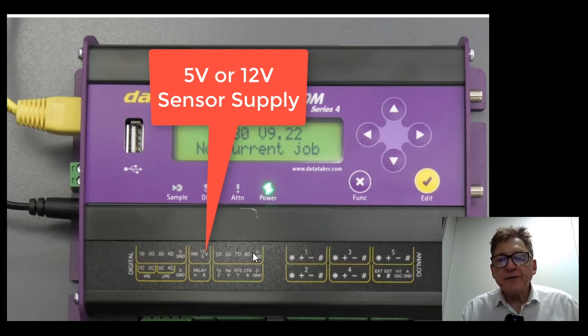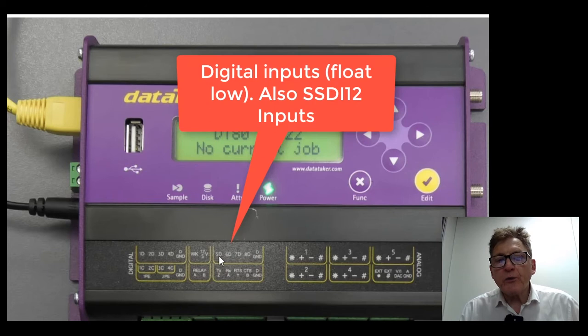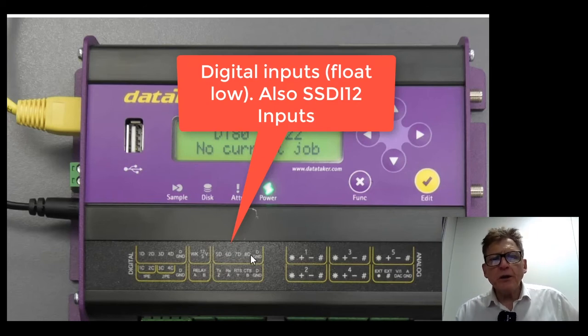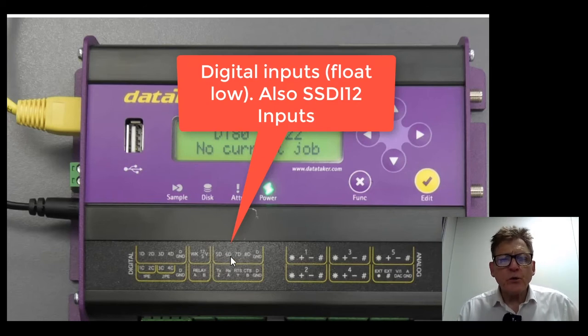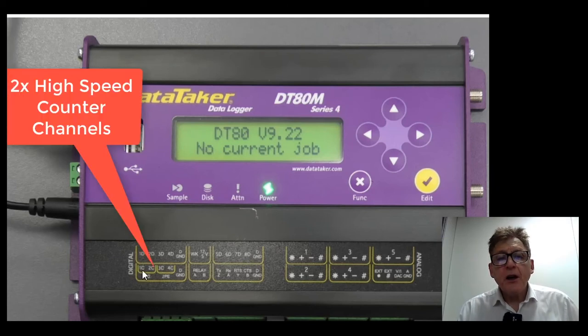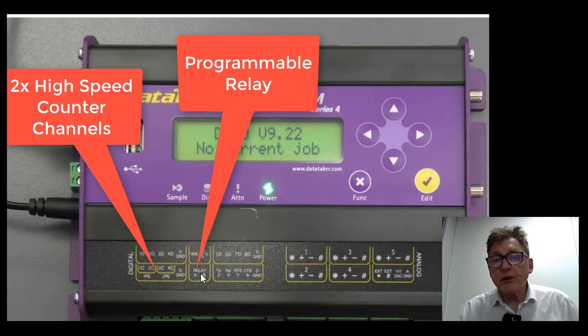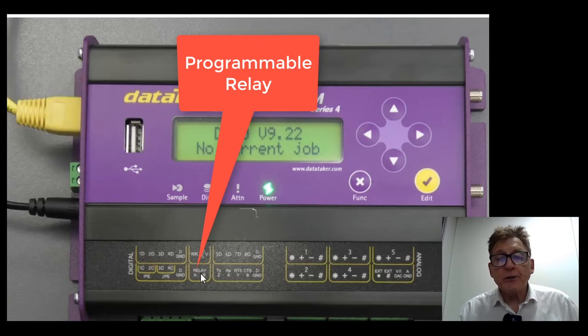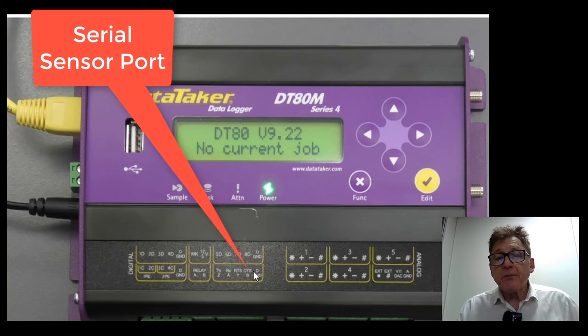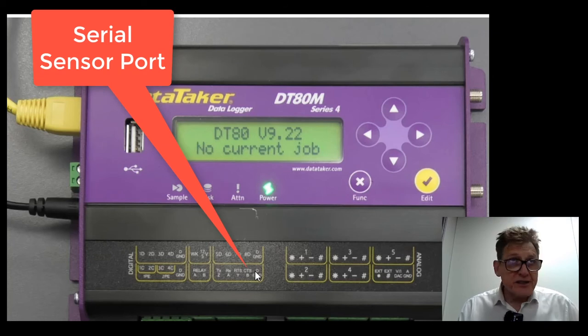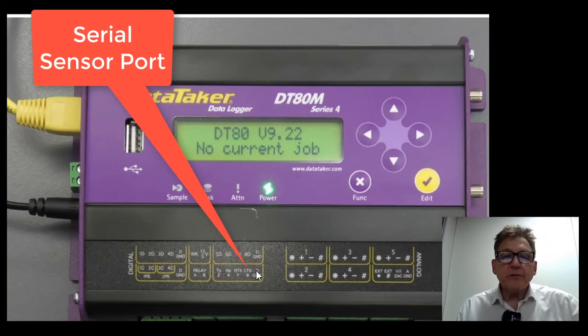Digital inputs, these float low, but they're also used for SDI-12. So you've got four SDI-12 channels, each of them can support multiple instruments. Two high speed counters here. This is a mechanical relay which can be controlled by the unit to open and close appropriately. A serial sensor port used for example for capturing GPS information.